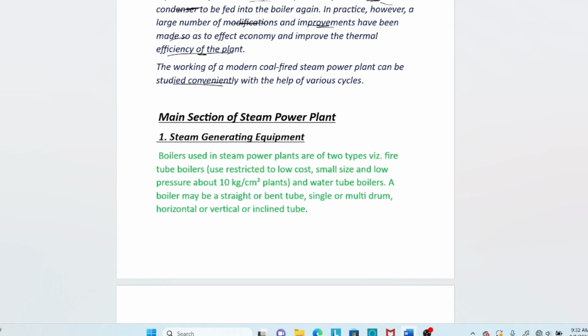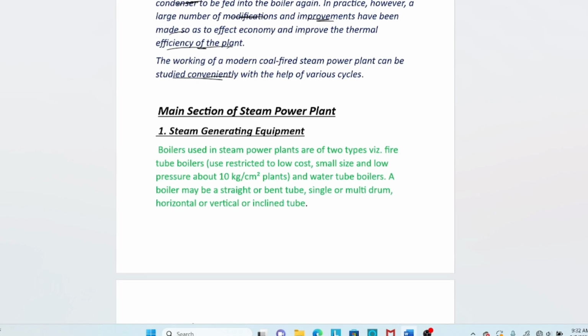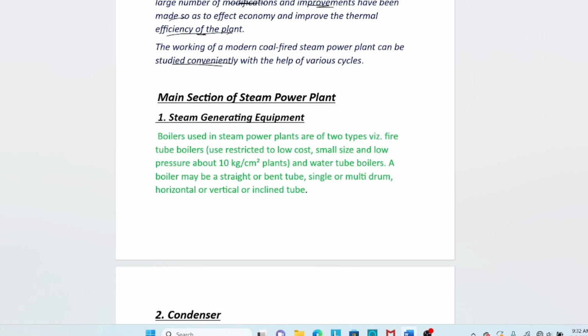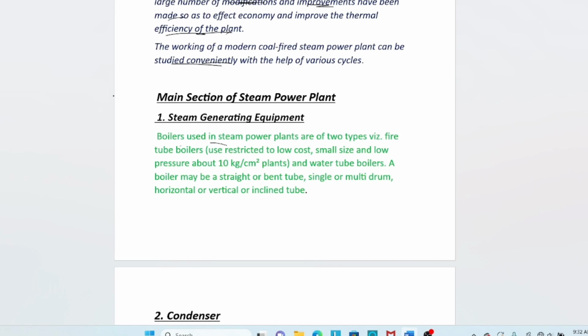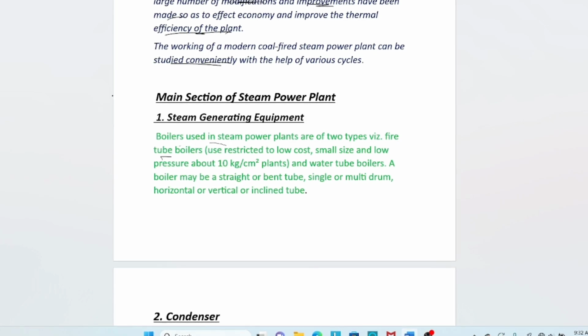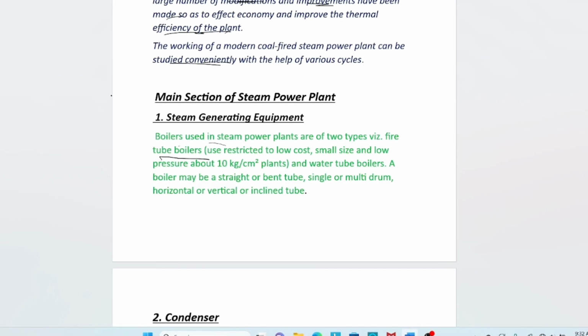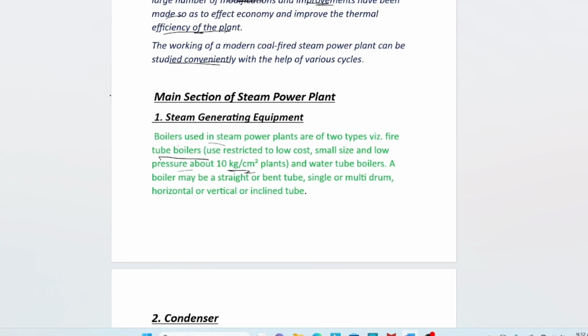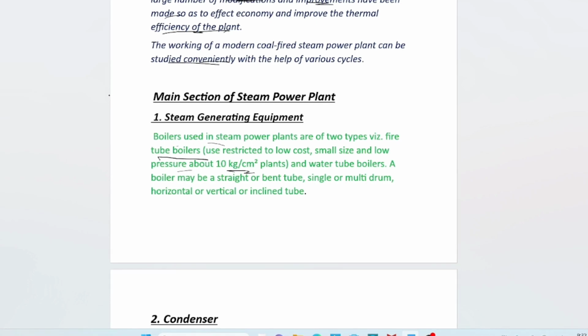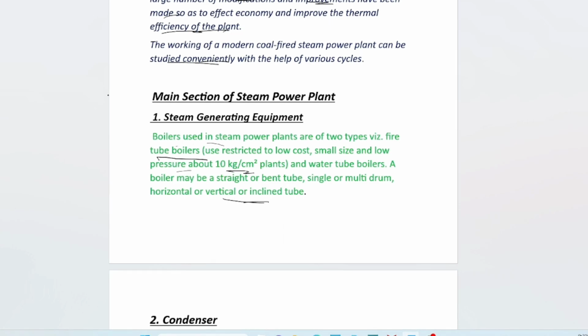First is steam generating equipment. Boilers used in steam power plants are of two types: fire tube boilers, whose use is restricted to low cost, small size and pressure up to about 10 kg per square centimeter, and water tube boilers. A boiler may have straight or bent tubes, single or multi-drum, horizontal, vertical or inclined tubes.